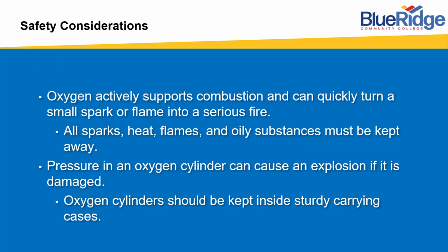So, some safety considerations. Oxygen actively supports combustion. It is not combustible or flammable, but in mixture with other ingredients it can help accelerate combustion or flames. It can quickly turn a small spark or flame into a serious fire. Remember also that these cylinders are always under pressure, and the rapid expulsion of that pressure can result in some sort of explosion or projectiles.